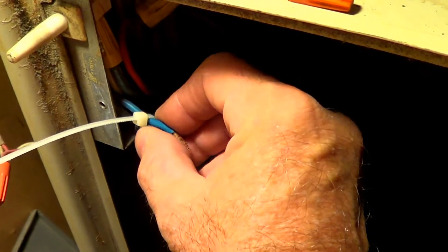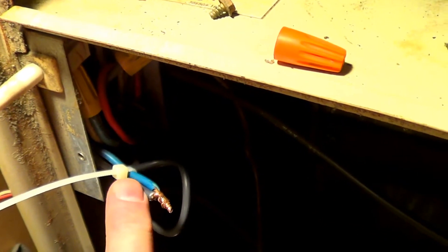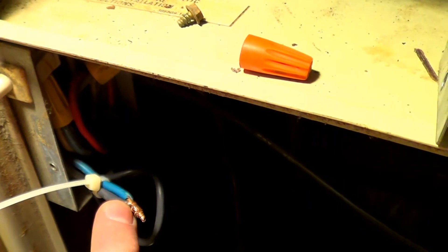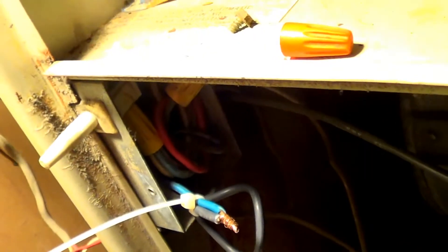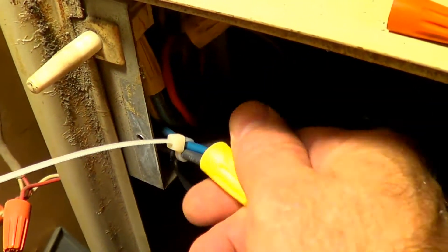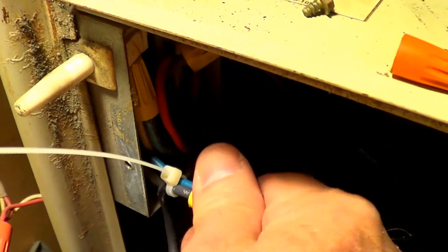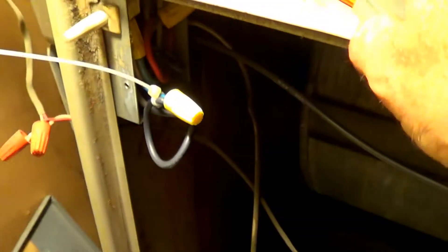I put a wire tie here to kind of strain relieve these two wires together. I've got to cut back the wire, which is this stranded wire. The plastic is really hard to cut back because it's so old. This looks like it's probably a number 14. It's hard to tell. This is a number 12. I've got these twisted together all sanded down. I put a wire nut on there that's a proper wire nut that's actually going to pull those in there. And this is the other one which barely engaged it. So that was the problem. I'm going to button all that back up and should be good to go.